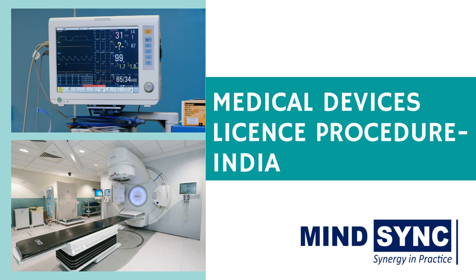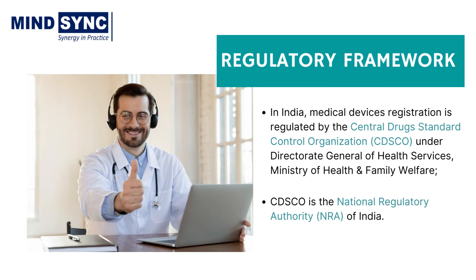MindSync is a professional organization that offers services like compliance, consulting, legal and advisory. After BIS certification, our next topic of discussion will be Medical Devices License Procedure in India. First, let us know about the Regulatory Framework for Medical Devices. Medical devices are regulated by the Central Drug Standard Control Organization, CDSCO, under the Directorate General of Health Services, an agency of the Ministry of Health and Family Welfare. CDSCO is the National Regulatory Authority of India.